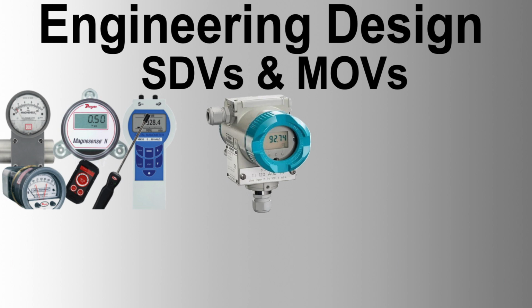Actuator mechanical design. Hydraulic actuators shall be capable of driving the valve at a standard speed of 1 inch per second of nominal bore against the maximum differential pressure acting across the valve. The stroke time of the actuator shall be adjustable. The actuator operation shall not be affected by the orientation or position of the valve and actuator. The actuator cylinder and other pressure retaining parts shall be designed and manufactured according to industry standards.